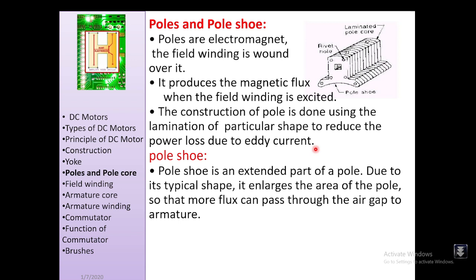The pole shoe is the extended outer part of the pole. Due to its shape, it enlarges the area of the pole so that more flux can pass through the air gap to the armature. The greater the area, the more flux reaches the armature. Poles and pole shoes are made of cast iron or cast steel.